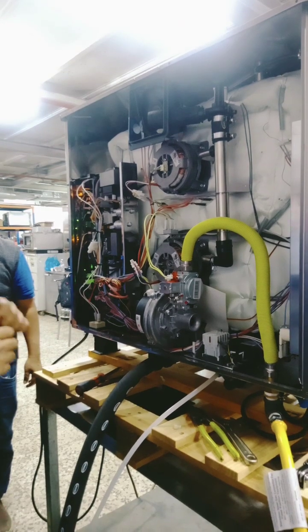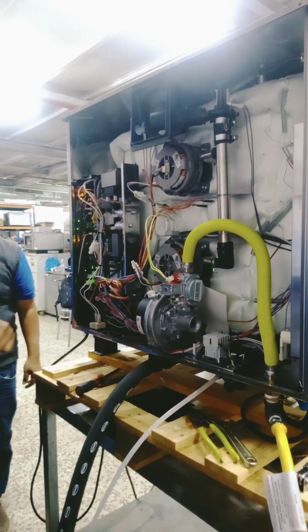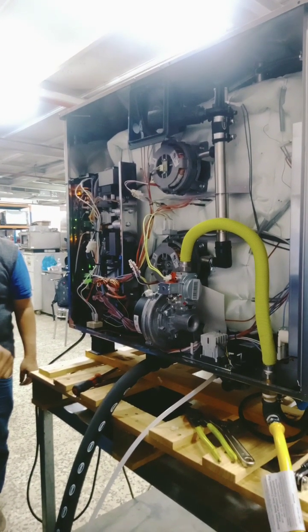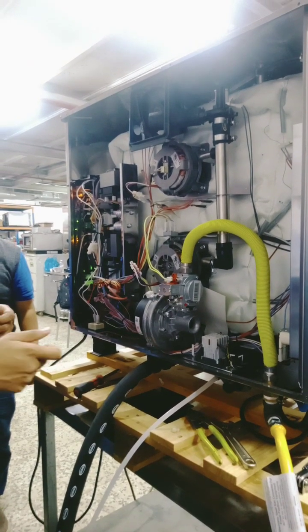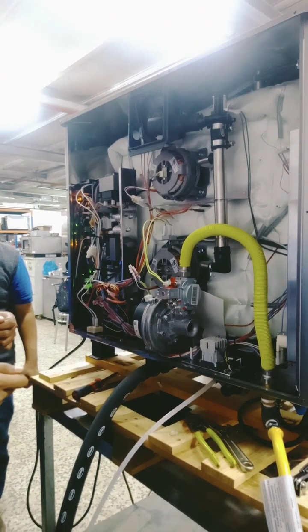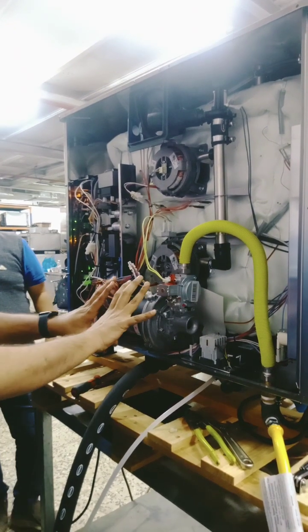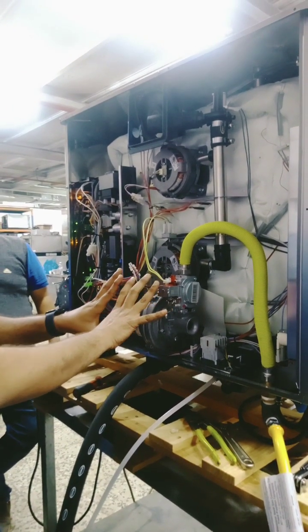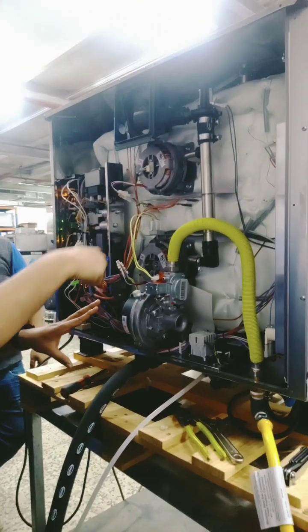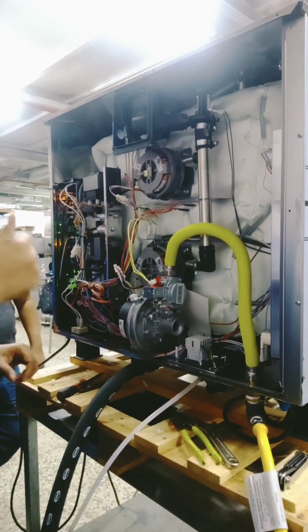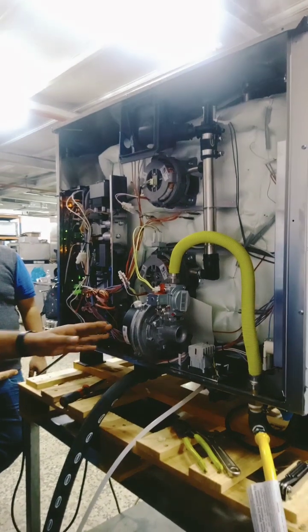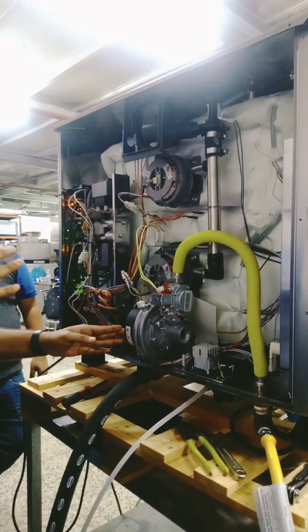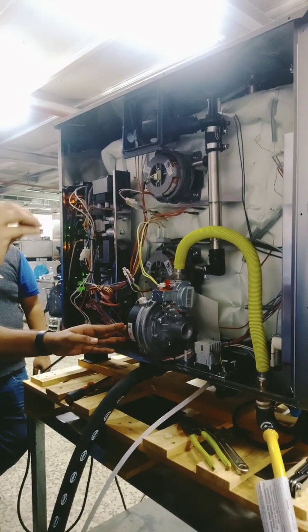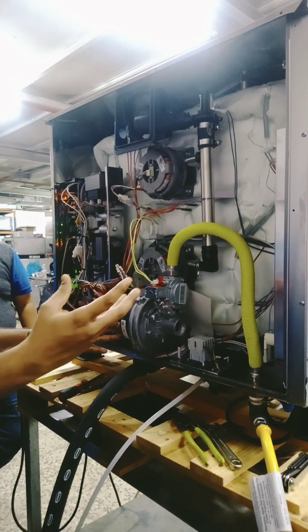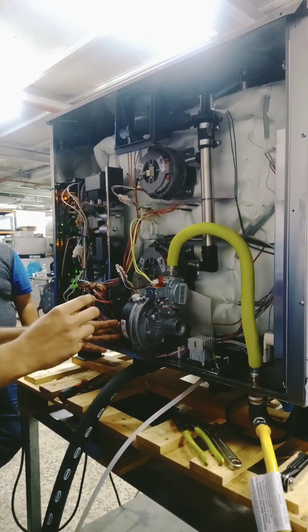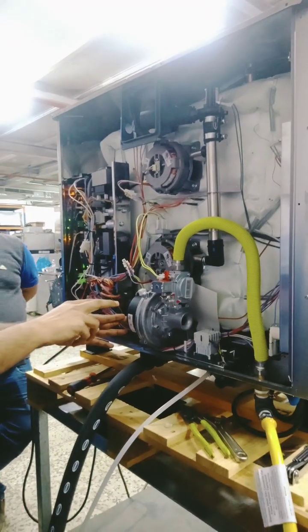Maybe on a floor standing oven, they clean the floor. While cleaning the floor using high pressure, like a shower kit or something, they could have sprayed this one, because there is a plastic cap here. Maybe water dropped in and damaged it. Or one reason could be higher voltage, because for this oven the maximum voltage is up to 260 volts. If it's higher than 260 volts, then it can trigger the blower.